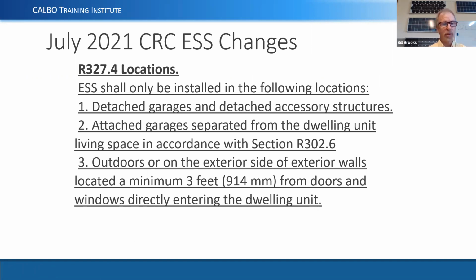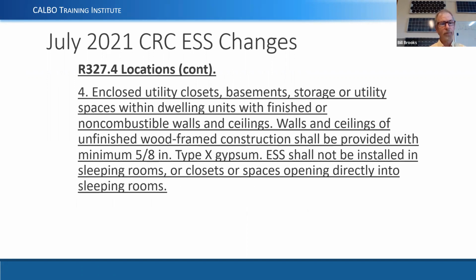Locations where we can put these things: we can put them in detached garages, detached accessory structures, attached garages, and outdoors on the exterior walls of the house, located at least 3 feet from doors or windows directly entering the dwelling unit. Directly entering the dwelling unit means going inside the living space of the house, not the attached garage. Okay, you can put ESS on the outside of an attached garage, and we'll show you a diagram of that in a second. And you can go right up to the garage door, right up to the side door of the garage, right up to the window of the garage, not a problem. You cannot go up to the window of a bedroom, for instance. It's got to be at least 3 feet away from that bedroom window.